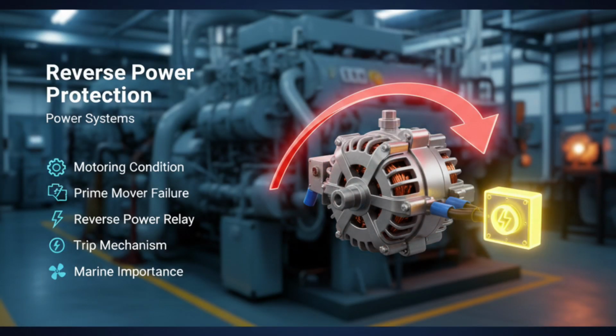Reverse power protection. Reverse power protection is particularly important in marine diesel generators. On your screen, the red backward arrow represents a motoring condition. If the prime mover fails, due to fuel failure, governor fault, or mechanical breakdown, but the generator remains connected to the busbar, it begins to draw power from the system and acts like a motor. This is dangerous because it can damage the diesel engine.